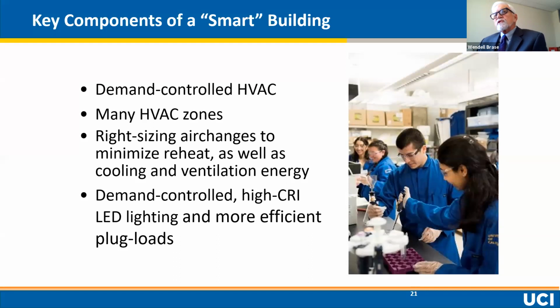So that means you need quite a few HVAC zones. You can't have one zone be half a floor. You have to have zones that are small enough that you actually get precision control using the kinds of sensors I just described. We found that right-sizing air changes actually results in quite a few benefits, including minimizing reheat, especially in an air conditioning climate like we have.